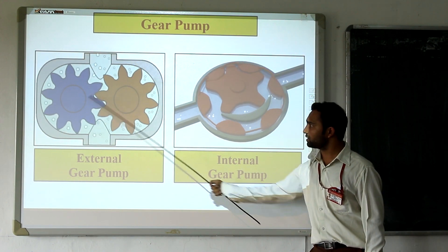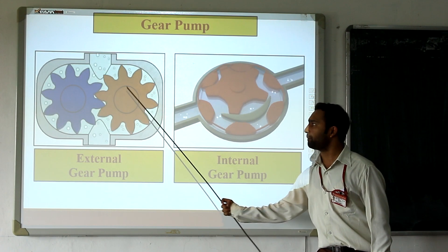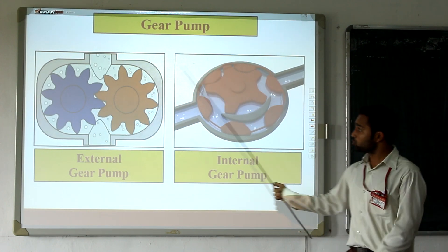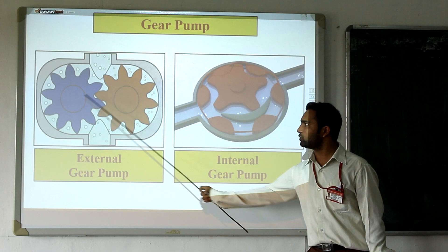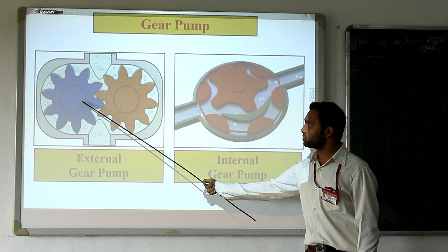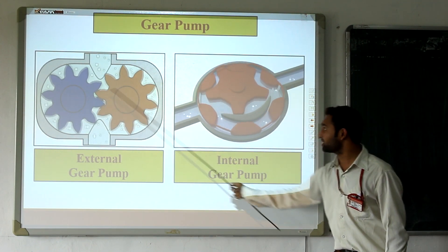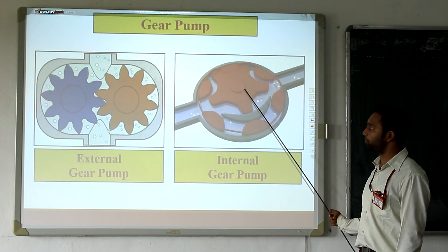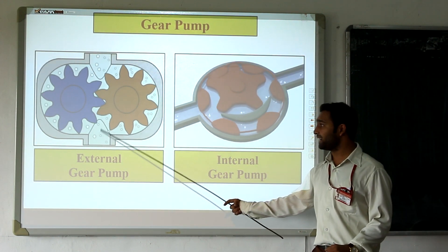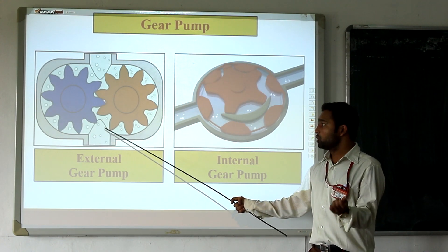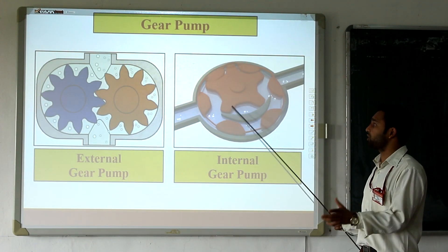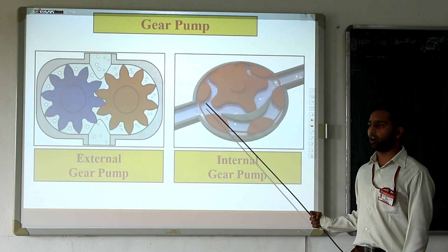Basically, in case of external gear pump, two separate shafts are there, so two bearings are used. In case of internal gear pump, only one shaft is at the central position, so the load is distributed differently. In the external gear case, there are more chances of bearing failure and more maintenance required, while in the internal gear case, there is lesser maintenance. Secondly, regarding the type of fluid handled: external gear pump is utilized for smaller to medium viscosity fluid, and internal gear pump is utilized only for smaller viscous fluid.